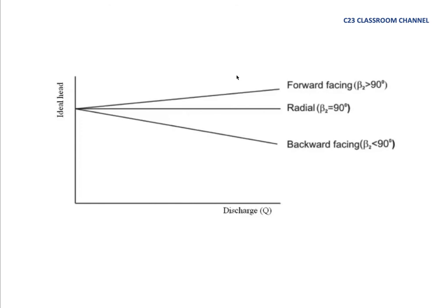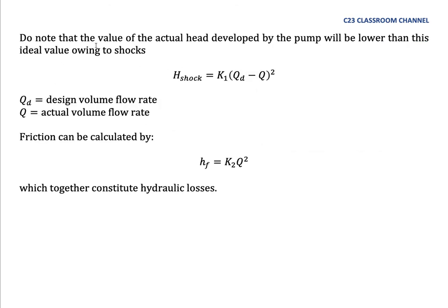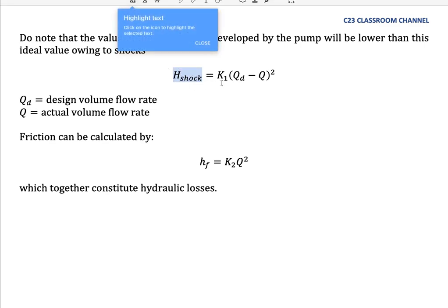Do note that the value of the actual head developed by the pump will be lower than this ideal value owing to shock, which means the theoretical head and the actual head will be different. The actual head will be lower compared to the theoretical head because there is resistance or losses. The losses we call h_shock equals k1 times (Q_d minus Q) squared, where Q_d is the theoretical volume flow rate, Q is the actual volume flow rate, and k1 is the resistance coefficient.